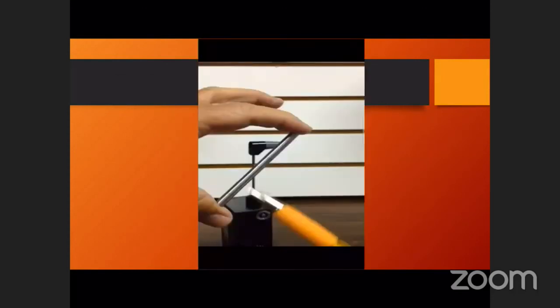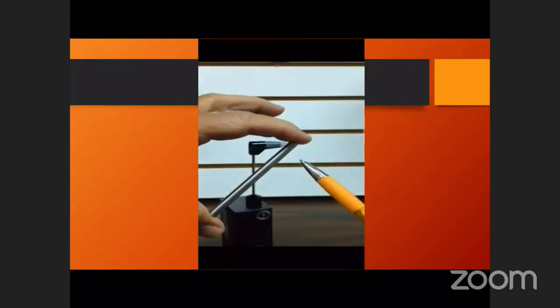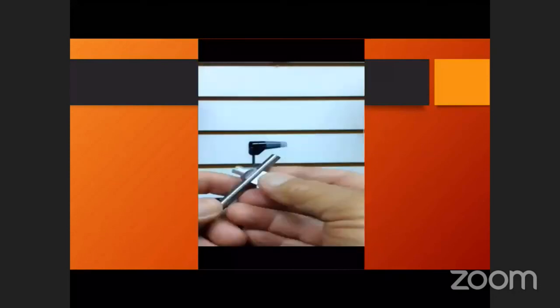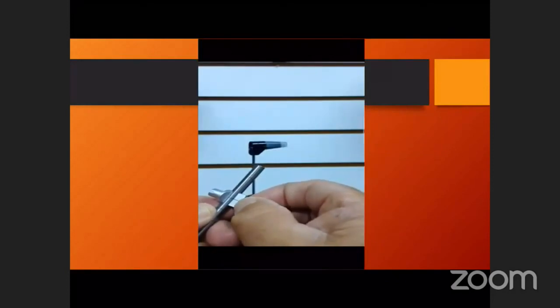So with a small video, I'd like to explain this. This is the calibration rod, and these are the 60 millimeter marking and 20 millimeter marking. This reference block is set here. It is at 20 millimeter of mercury. And that is how it is put into the box. And then you see when it is moving on the 2 mark, you just see the prism, it will move back. The calibration should be such that it should not go beyond the 1 mark. So 2 corresponds to 20, 1 corresponds to 10. It should lie between 18 and 22. If that is so, the calibration is good. If it is going beyond 18 or 22, the calibration is not good, and we have to send this to the service people who will do it from their end.